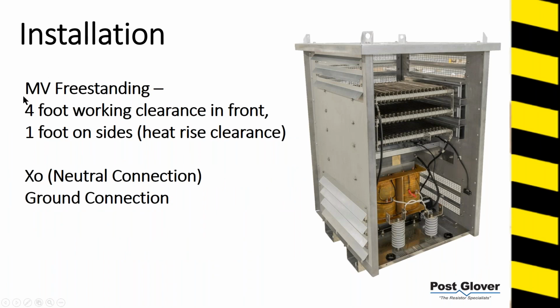In terms of working clearance, for any piece of equipment you're going to need working clearance on at least one side. So you would need that 4-foot working clearance. Typically it would be in the front for the unit I just showed you. For a unit more like this, you would probably pick the side which is more easily accessible. You need to have 1 foot on the side. That's not electrical clearance. For our units, typically 385 degrees C for continuous operation, you need to make sure there's some separation and some airflow. So that's why there's that.